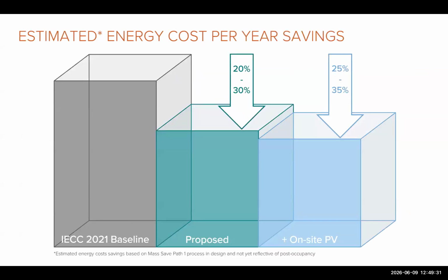So here we're looking at estimated energy cost savings per year compared to a baseline. The baseline and proposed energy analysis were done through the Mass Save process. Comparing the proposed project to an IECC 2021 baseline, there's potential energy cost savings of 20 to 30%, which increases to 25 to 35% with the on-site PV.